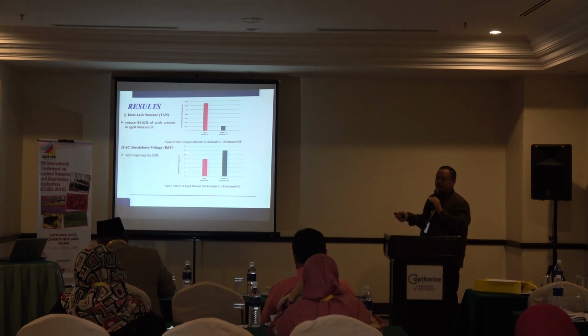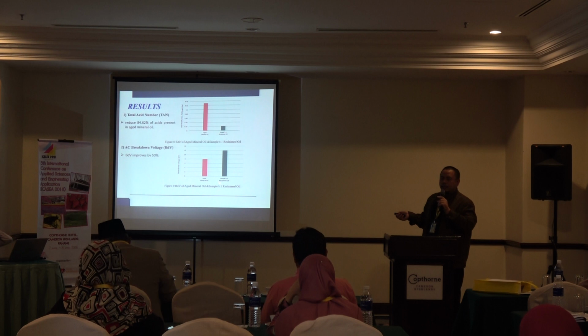So to make the recycling better, I have some ideas. We can improve by increasing the number of reclamation cycles, because here I'm presenting only one cycle. For the first reclamation cycle, the oil changed to light brown. If we do more cycles, maybe it will change to a lighter one and become bright. Then it might increase the breakdown voltage. According to the theory, a higher breakdown voltage means the oil has no conductive particles inside, a reduction of suspended particles, and is also related to the gassing tendency of the oil.